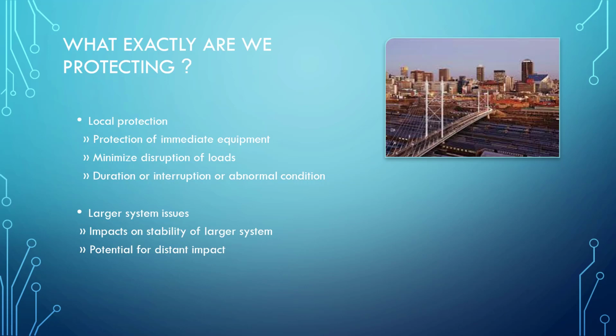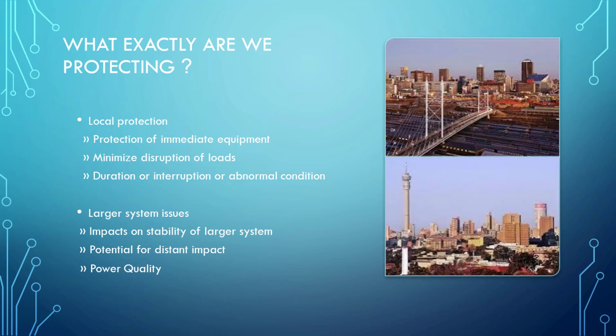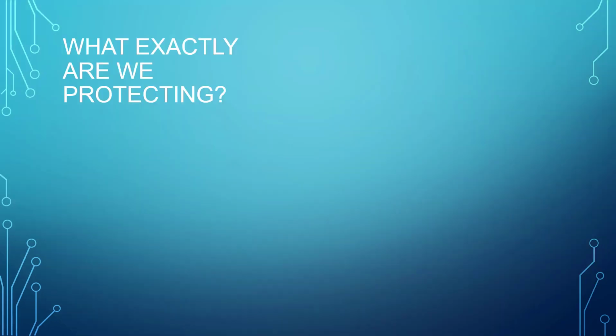You also have to ensure the power quality, because if your power is getting interrupted all the time, that will affect the quality of power you are supplying to your consumer, because your equipment will be unstable. So big cities whose economies solely rely on a stable power supply depend on these objectives of protections to be assured. Failure to protect the system in case of a fault will result in what? In fire. Because if you don't ensure a reliable protection, the integrity of the system will be compromised.